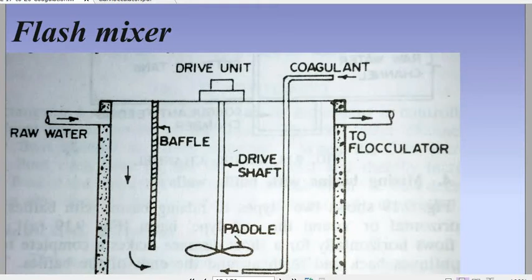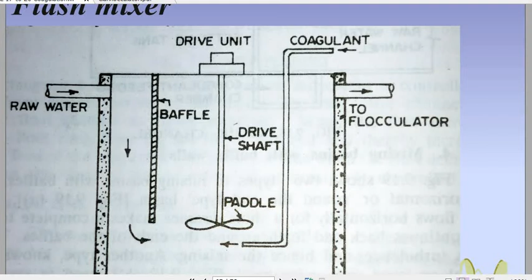This is the most important device, the flash mixer, in which the coagulant is mixed thoroughly with the raw water. You can see the arrangement here. It is a concrete section; the outer section is made of concrete. An inlet and an outlet are provided here, and one baffle plate is provided, and a driving unit, that is the motor, is provided, so that the shaft and blade or paddle are driven. The coagulant feeding pipe is also provided just at the bottom of the paddle. This is the coagulant mixing device, and after the mixing the water goes to the flocculator.